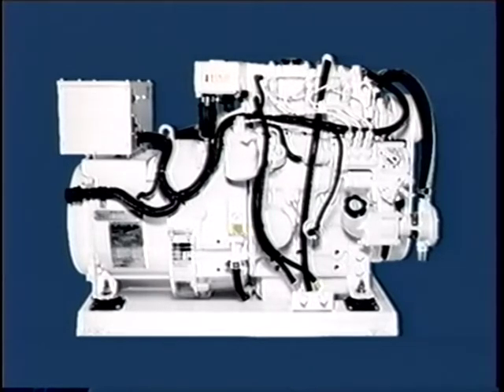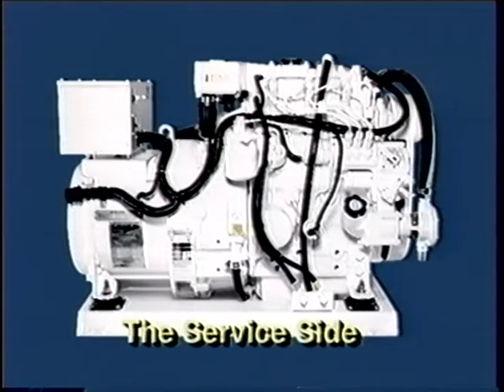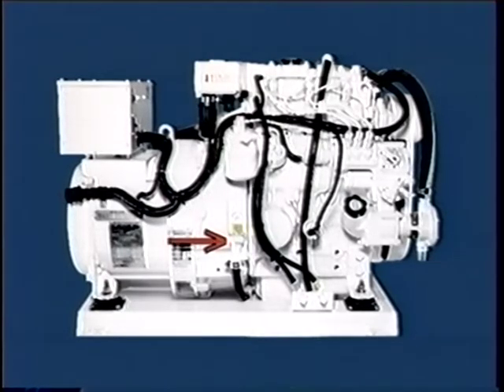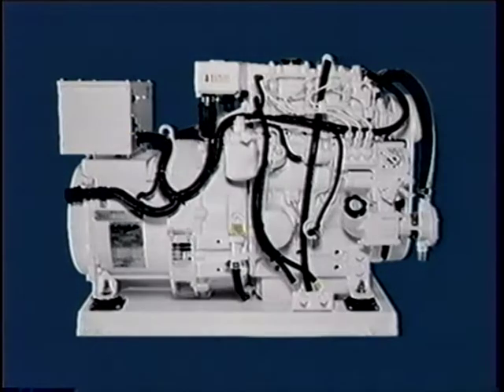design feature that is built into every Northern Lights generator set. As we call out the main components of the system, you will see that we have located all the routine maintenance points on one side of the unit, the service side. The oil drain tube, the oil filter, the oil fill cap, the dipstick, the seawater pump, the fuel filter, the air filter, the generator J-box, the DC control circuit breaker, and the AC voltage regulator circuit breaker. Please refer to your owner's manual for the location of all other components.